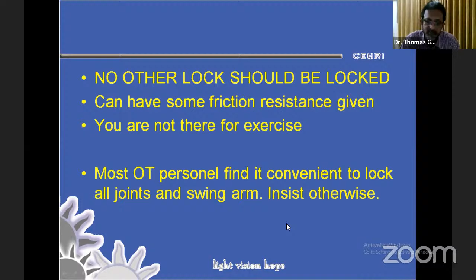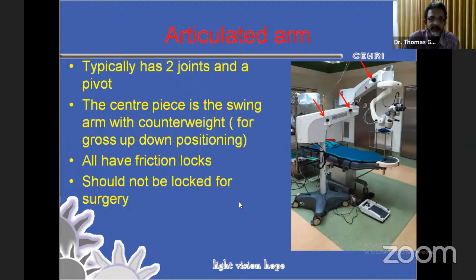The articulated arm typically has two joints. There is one above the footplate and one more joint, and a pivot onto which the microscope itself is attached, so that you can rotate the microscope finely. This allows you to move it around on the XY plane quite a bit. And the centerpiece is a swing arm with a counterweight at the other end. All of these have friction locks, and these should not be locked for surgery. They should be relatively free for movement during surgery.